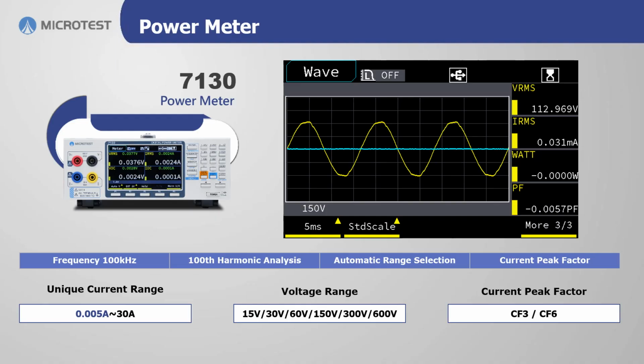The Microtest 7130 power meter is equipped with waveform analysis capabilities. Its testing screen not only displays numerical values but also allows waveform analysis. With a bandwidth of 100 kHz, it features a 100th harmonic analysis, automatic integration, and measures parameters like current peak factor. The unique current range spans from 0.005 amp to 30 amp, making it suitable for production line testing in industries such as photovoltaics, power supplies, inverters, and household appliances.